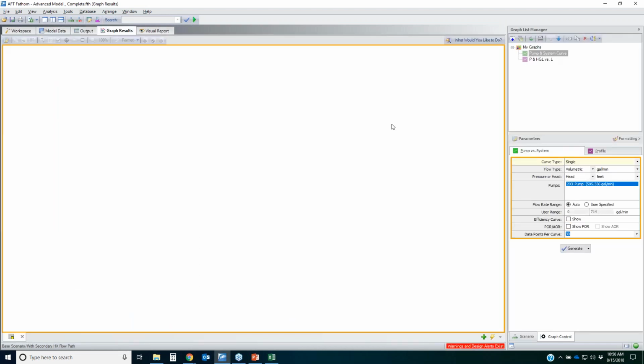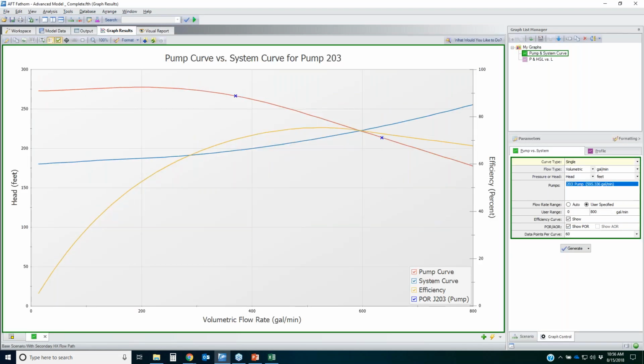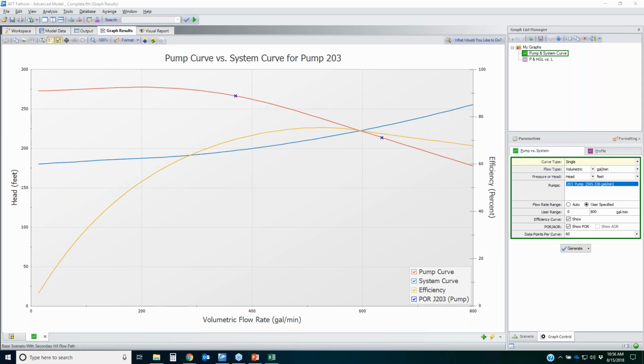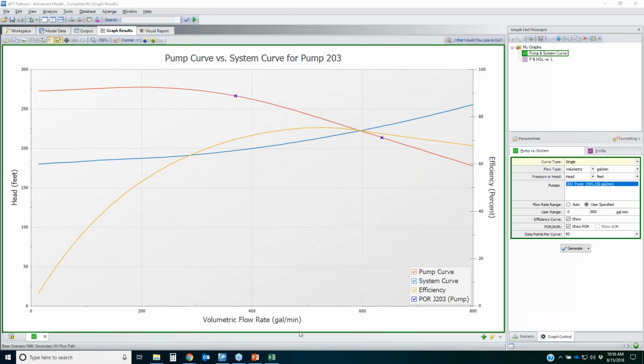Well, here's what my pump and system curve looks like for that expanded system. Let me double click on that again. So here you go. As you can see here, you are operating still between these blue X's, but look, you're getting a little bit further away from that best efficiency point. Well, what I did was I took this data and I put it into a spreadsheet, not that spreadsheet, that's my other spreadsheet, and I actually plotted the system curves together. Let me open that up and show it to you.